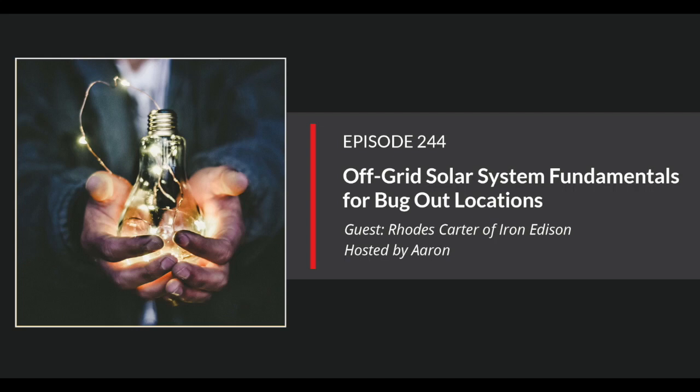As I said, a fossil fuel generator is the most common backup to have. Especially in the winter months, I try to design solar systems I'm working on to get through Christmas, because that is traditionally the highest electrical load you're going to have and the least amount of solar production. So if you can make the numbers line up so that you can get through Christmas week, then you've got a great solar system. But doing that may make the price of the system a little too high.